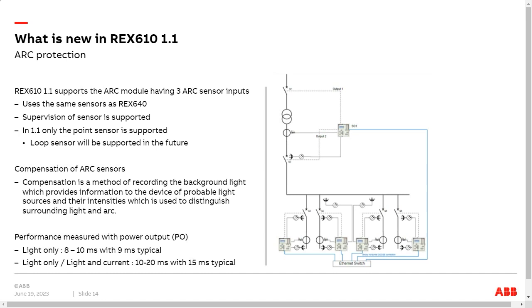In many cases, these times are much better than what you get using normal protection. Also, looking at the historical values and the sales figures, it's quite typical that even though people are using arc protection, they don't tend to order the high-speed output. So it's a little bit of marketing, I would say, that you need to have the high-speed outputs for arc protection. In practice, quite many don't order it. But yes, you can improve it even further by having high-speed output as well.